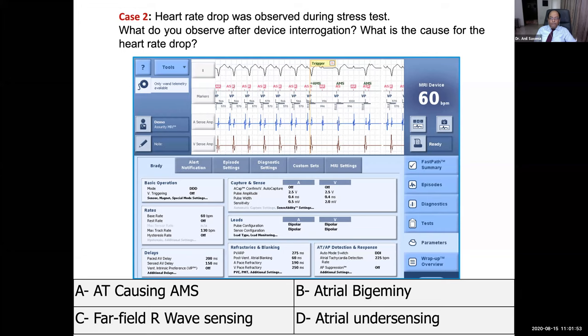Excellent. Most of you have correctly diagnosed it as far-field R wave sensing. As shown, the ventricular signal can sometimes be sensed in the atrial signal. So we can focus our attention on the atrial sense channel, and we can see there are two spikes. At a lower rate it may not matter much, but as the rate increases and the count doubles, it may reach the tachycardia detection rate, triggering an automatic mode switch.